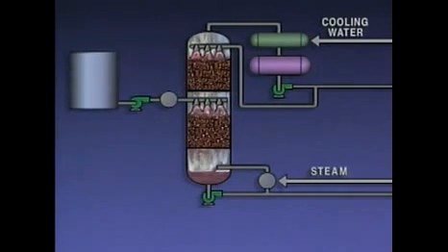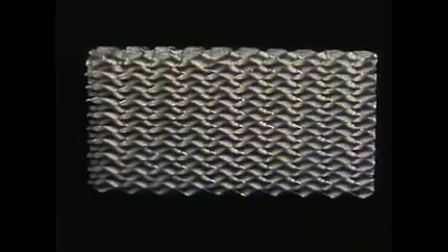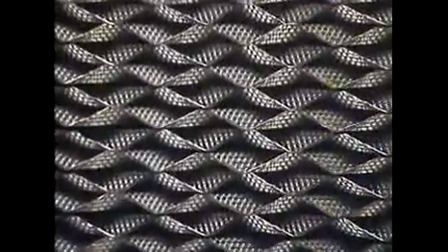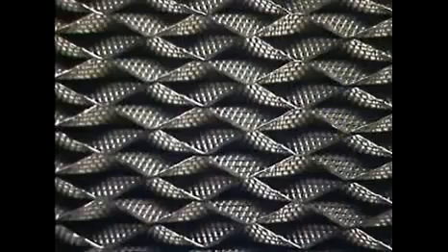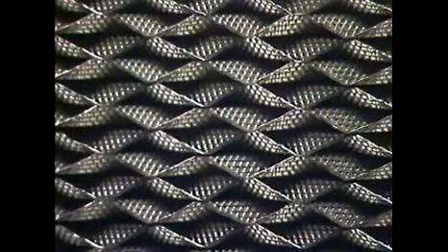Packing can be made from many different materials, including porcelain, copper, aluminum, and iron. The main requirement is that the material must be compatible with the liquid in the tower and the conditions under which the tower is operated. This is a section of another type of packing from a distillation tower called a packing grid. Each layer in the grid has spaces for vapors to rise through the packing on their way up the tower. Liquid flows over these surfaces, which channel the liquid as it flows down the tower. The packing grid provides a great deal of surface area where contact between the vapors and the liquid can take place, so heat transfer is maximized.